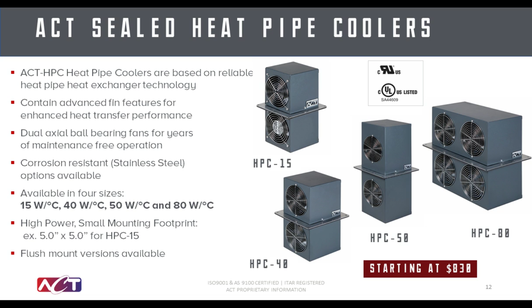Again, similar to the model number corresponding to a certain thermal conductance value of the HSC product line, if your application has a 20 degree C delta to work with and you're using an HPC 80, you would get approximately 1600 watts of heat dissipation capability. Again, this calculation works with any delta with any of the model numbers to get not only the specific configuration you need for your application, as well as the number of units you may or may not need.